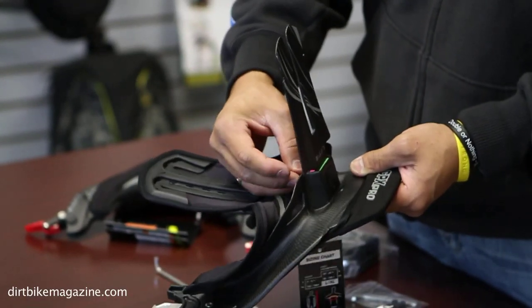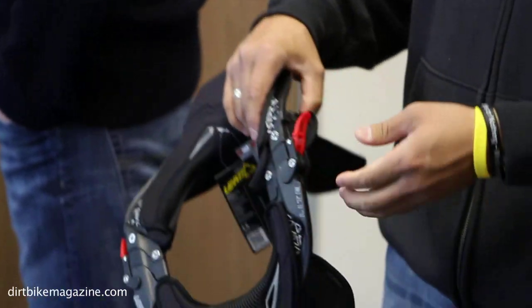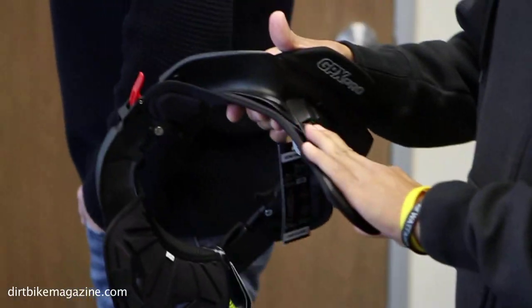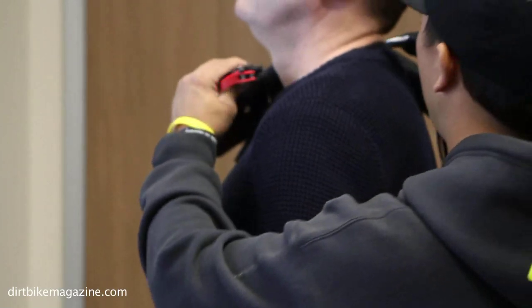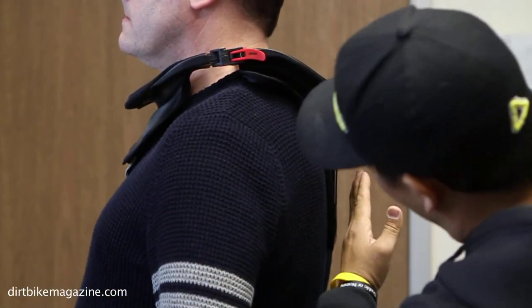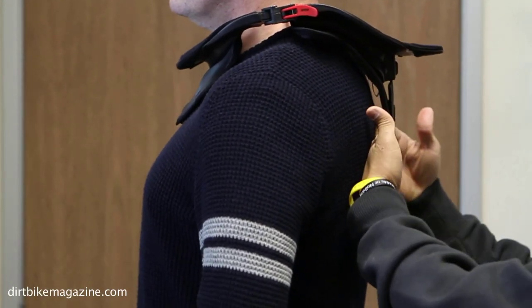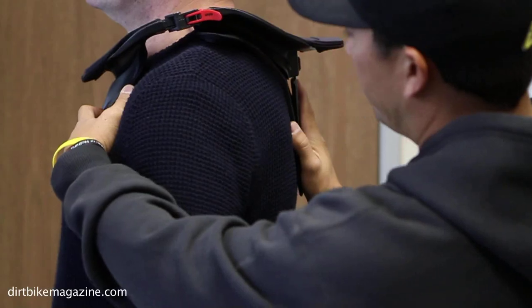Okay, so our final adjustment as we move through the fitment of this particular brace: what we've done is added the 20mm pins, which is the largest pin available in the bag, and on this final one I changed the angle of the back thoracic piece. We'll go ahead and put this on now and see how this fits a little bit better. You can see that it does match the curvature of his back much better. I've angled it out and I like the fitment from front to back — I can slide my fingers in here, there's a little bit of pressure but it's not too tight. I would call this a good fitment. I'll see you next time.